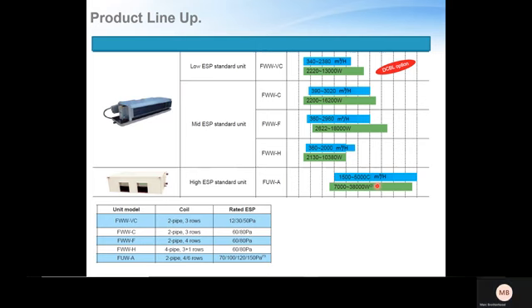The coils, generally 2-pipe with 3 rows. Here for the better latent heat removal, we go for the 4-row. Then from the FWWH range, we have the 4-pipe, so that would allow for hot water and cold water, as well as the 4 rows for nice dehumidification. And then the high ESP 2-pipe with 4 to 6 rows for some very good fresh air applications where you need a lot of dehumidification. We have some good ESPs, 50 pascals, right up to 150 pascals. The water coils have all been tested up to 1.6 megapascals of dynamic water pressure.